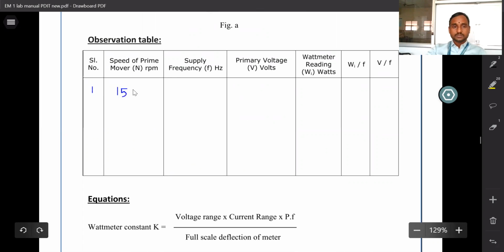So for the first reading, suppose 1500 rpm. For 1500 rpm you will get 50 hertz, as it is a 4-pole machine. The speed can be calculated for the corresponding frequency. So for 50 hertz, next is 47.5 hertz. Next reading you have to take for 45 hertz, and similarly 42.5 hertz, in decreasing order, and 40 hertz.